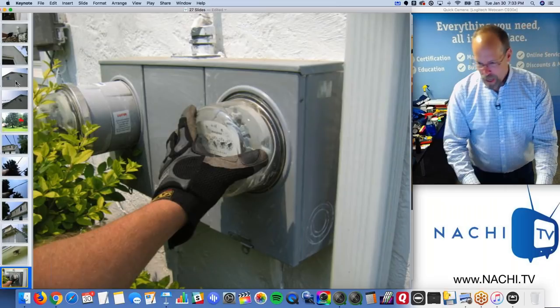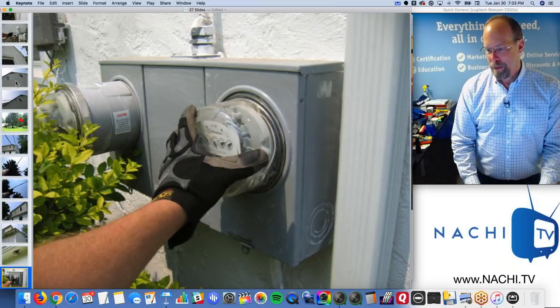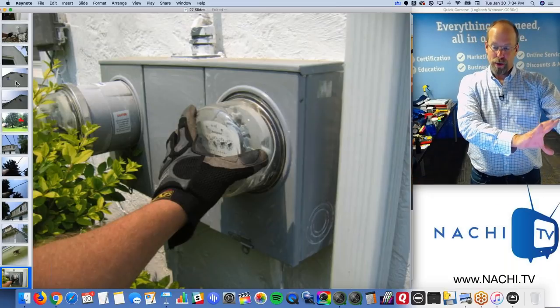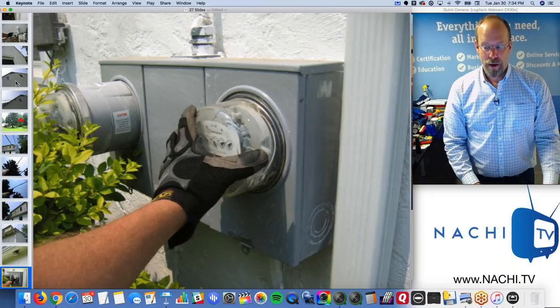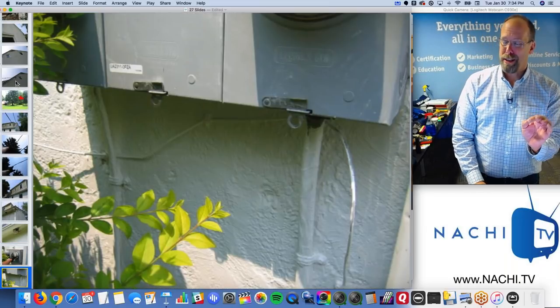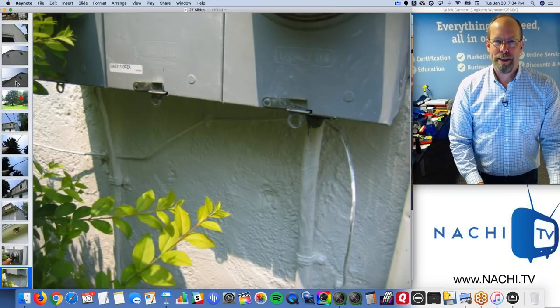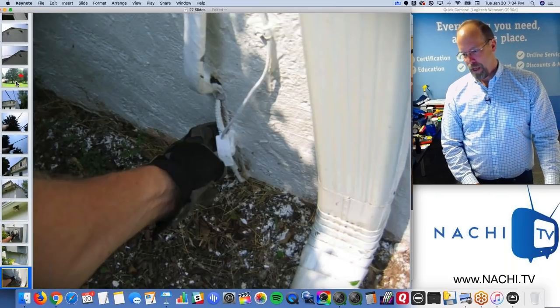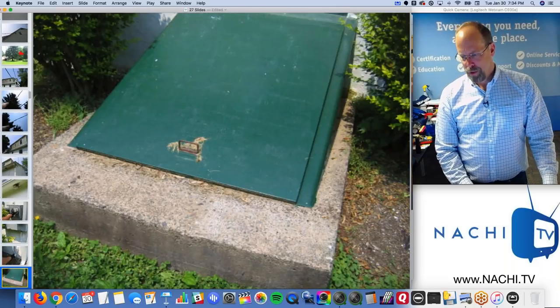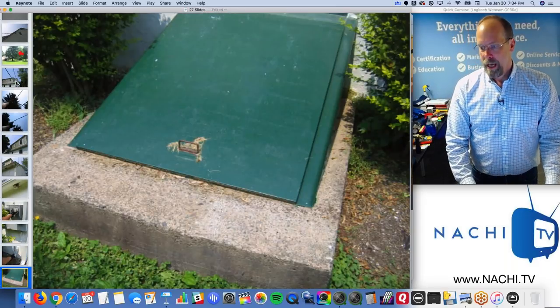So right now I have the electrical meters. Main meter for the electrical panel. They used to do this, a sub meter just for the hot water tank. So I'm expecting an electric hot water tank that's on a separate meter, kind of designed to save energy. That was the idea. Grounding wire from the electrical panel to a rod, good.